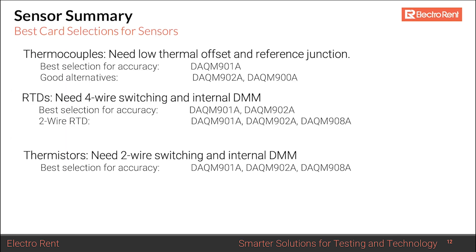Here is a summary of sensors and the best cards to use for each. For thermocouples, you want the lowest thermal offset, so the DAQM901A is the clear winner. If absolute low thermal offset is not critical, the DAQM902A and DAQM900A can serve as alternatives.